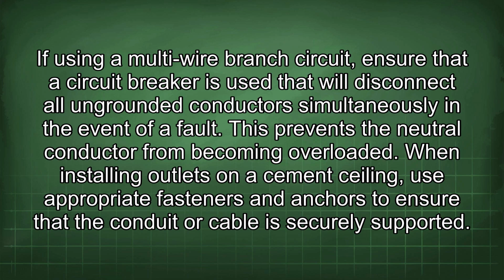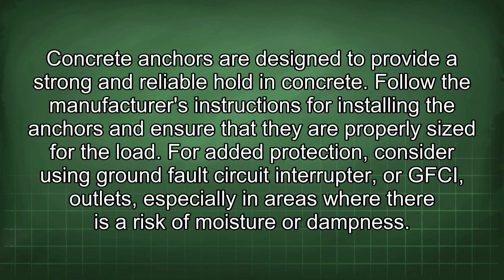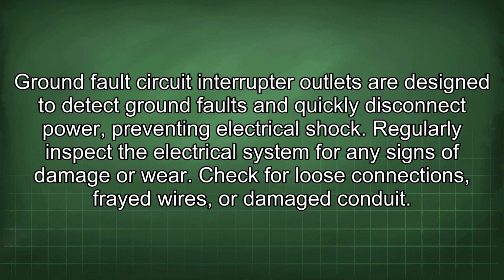When installing outlets on a cement ceiling, use appropriate fasteners and anchors to ensure that the conduit or cable is securely supported. Concrete anchors are designed to provide a strong and reliable hold in concrete. Follow the manufacturer's instructions for installing the anchors and ensure that they are properly sized for the load. For added protection, consider using ground fault circuit interrupter, or GFCI, outlets, especially in areas where there is a risk of moisture or dampness. Ground fault circuit interrupter outlets are designed to detect ground faults and quickly disconnect power.